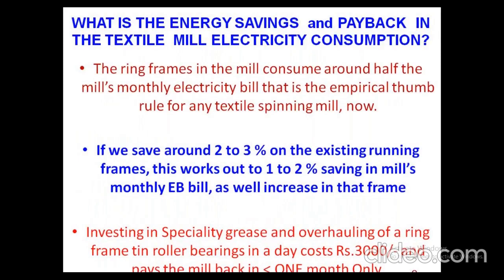Coming to the case studies of textile mills, where 50% of the consumption is on the ring frame, we are very much aware of this. It's a thumb rule only: let us say the mill is consuming 10,000 units per day, then 5,000 units per day is going towards the ring frame. Why I'm suggesting this now is that condition monitoring is not only ultrasonic or infrared, but also oil analysis or grease analysis, for the given textile mill or for any industry where we can achieve this.